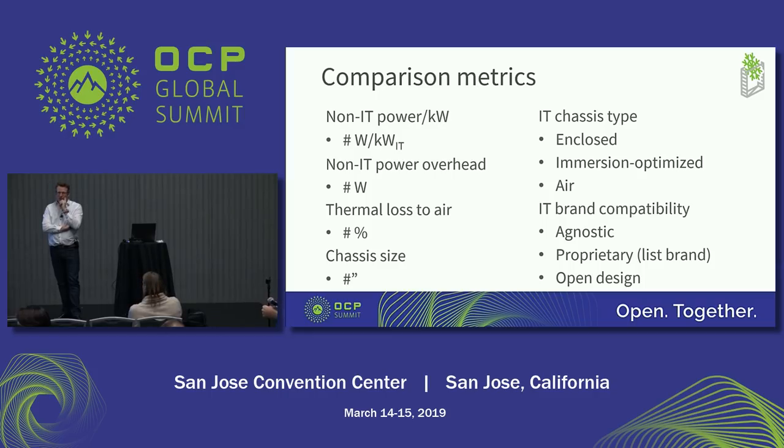And that's exactly the point. In my experience with that type of measurement, you're going to have to factor in the power factor. And you have to look at the curves of the power that goes in and comes out, because that actually affects the actual wattage that is being converted into heat. And these things never really add up, in my experience, if you're just using the power inputs and the thermal output calculations, also the tolerances of the thermal sensors.